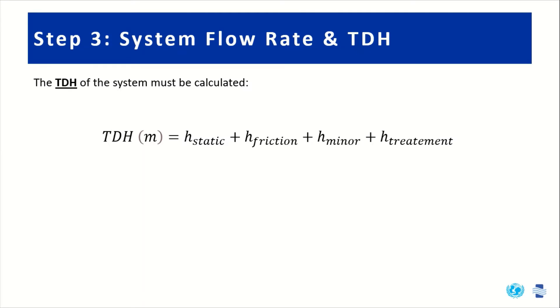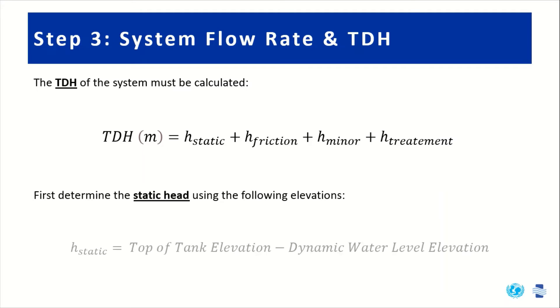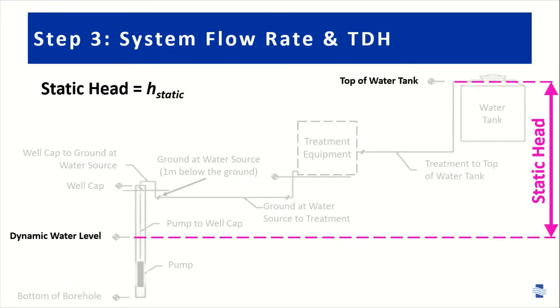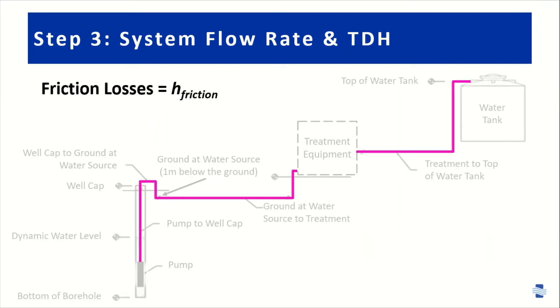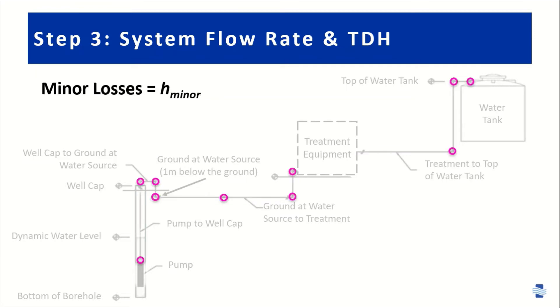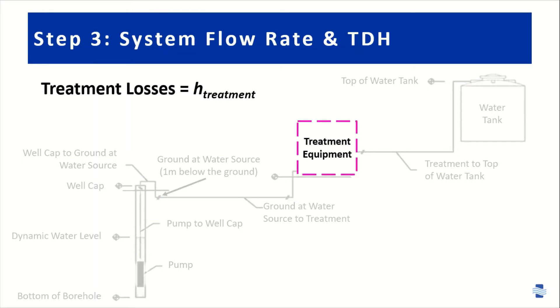The TDH of the system is calculated using the following equation: static head plus friction losses plus minor losses plus treatment losses. First, we determine the static head using the top of tank elevation minus the dynamic water elevation — the vertical distance between the top of the water tank and the dynamic water level. Next, friction losses are caused by friction as water passes through the piping. Minor losses occur at bends, fittings, valves, or instruments such as pressure gauges. Lastly, treatment losses occur when water flows through the treatment system.